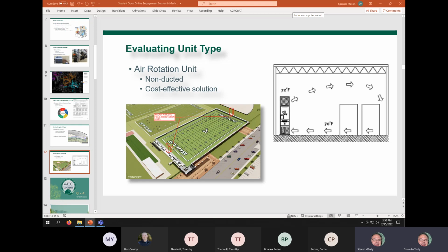Multiple units were discussed during our design process—we looked at whether it was best to put them here on the end zones, centered, or staggered across the sideline. That was another evaluation. The thought process came down to where our service entered the building: decreasing our line size after that location would be the most cost-effective for this project, since we'd only need to route a smaller line to this side rather than larger piping runs all the way along the side, with two units centrally located on the sidelines.